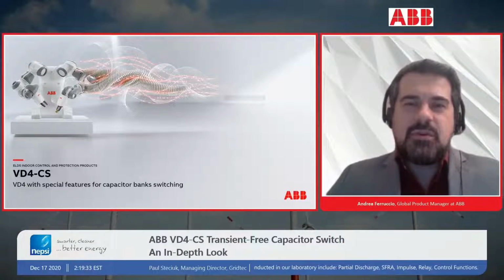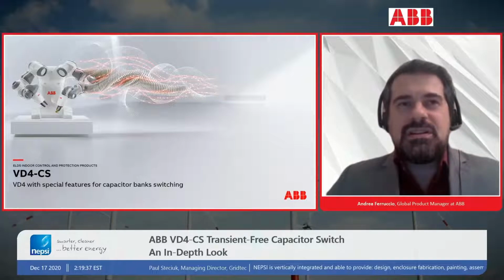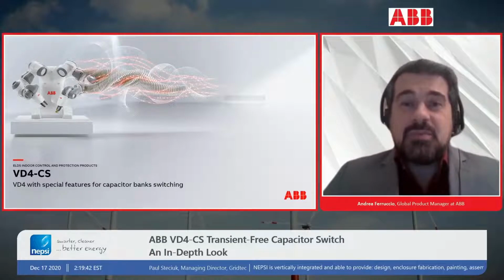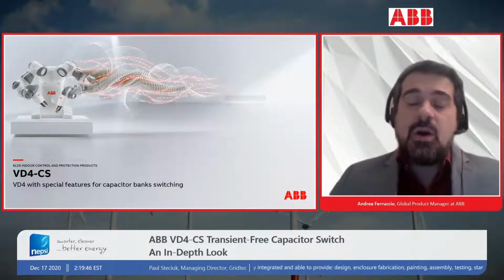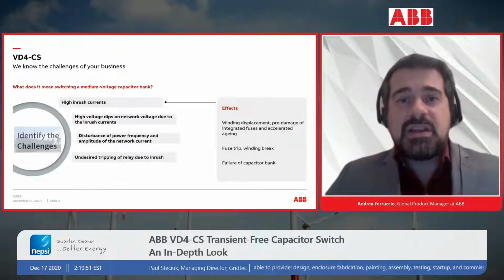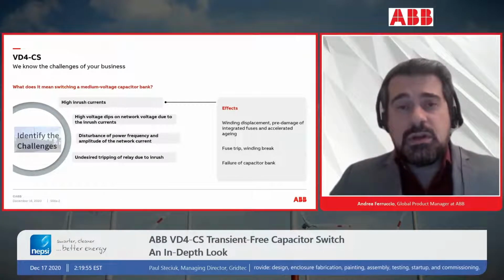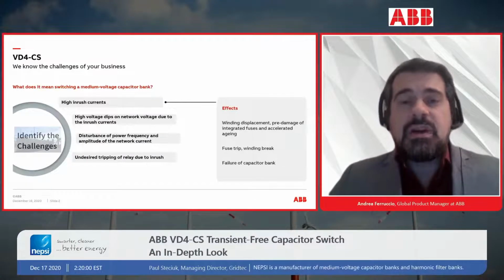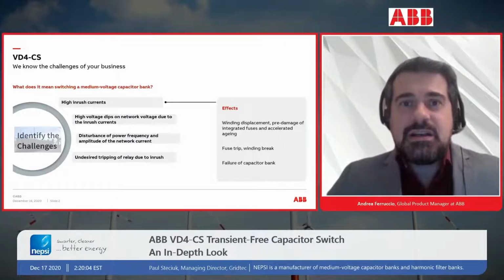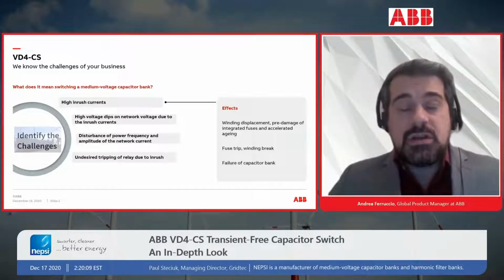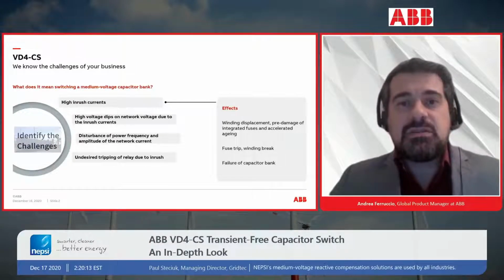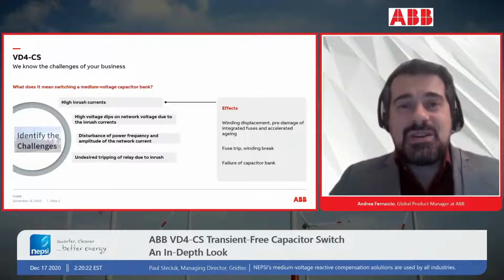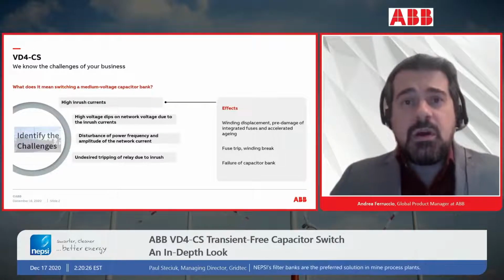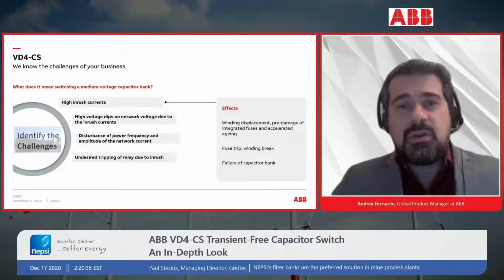A solution specifically designed for facing and solving those undesired phenomena that appear whenever a capacitor bank is switched. We all know how crucial a capacitor bank is in its network, and how important its role is. But due to its physical characteristics, whenever we open and close a cap bank, capacitive load means capacitive current, and something happens that is not desired. It can have an impact, short or long term, on the capacitor banks themselves, but also on all assets connected to the same network. Thank you for your attention.